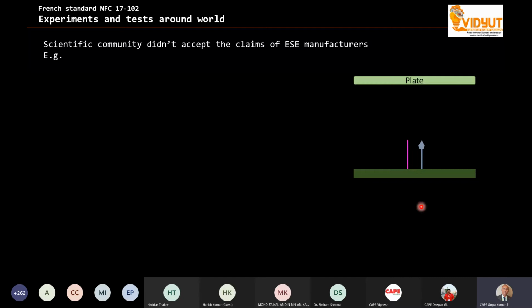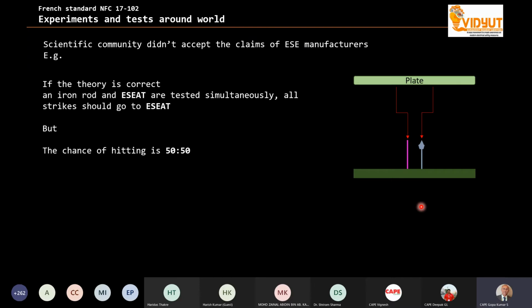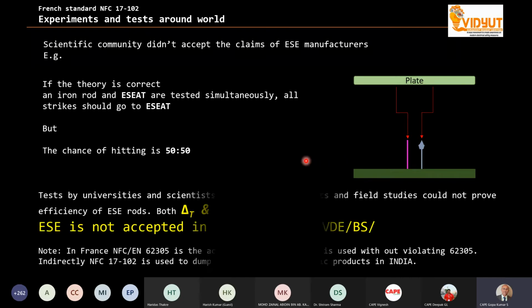So what scientists did, they connected an iron rod and an ESE rod, and if the claim of ESE vendors is correct, if the ESE is more efficient, and if you put 100 strikes, out of 100, all the 100 strikes should go to the ESE rod. So they made the charge, they did the testing, and finally the result is, if the theory is correct, when the iron rod and ESE are tested simultaneously, all strikes should go to the early streamer emission air termination. But it is not so. It's about 50-50. In some cases, ESE will have 60, the normal rod will have 40. In another case, sometimes the normal rod has 70 and the ESE has 30. So the claim of the ESE rod companies is absolutely wrong. This is one of the ways it is proven.